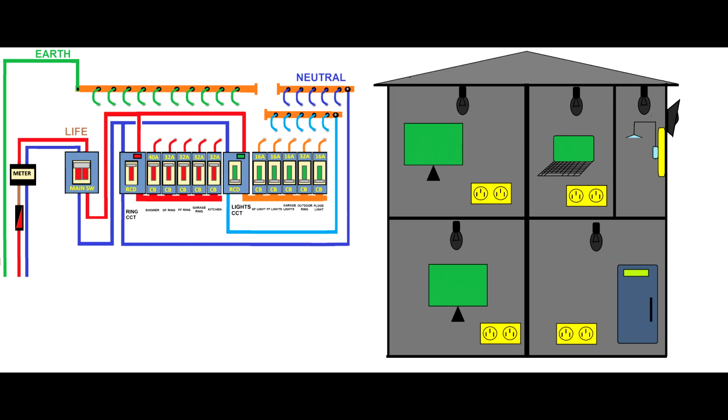If I'm not an electrician, without opening the distribution board, I will turn all the circuit breakers off. Once I turn all the circuit breakers off, I hope there is not an earth leak between neutral and earth, because that will change the situation, I explained it in the last video. Then I eliminate somehow the fault, and then I will turn on the circuit breaker. If the circuit breaker is not tripping, I will use the test button.